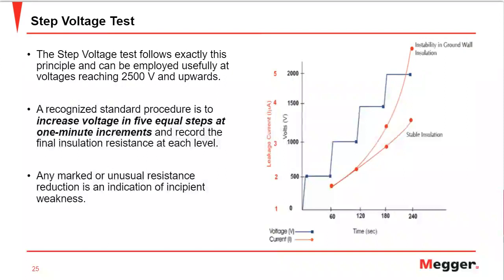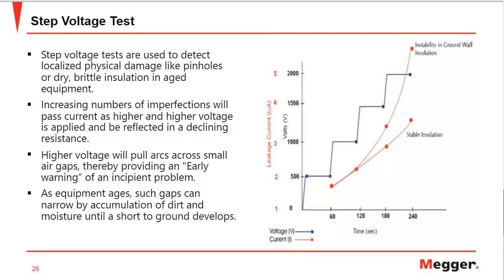Also, as we discussed previously, it increments in 5 equal steps, stays there for a minute on each step, and then calculates the total leakage current. Step voltage tests are used to detect physical damage like pinholes and brittle insulation in aged equipment as well, because we increase the voltage more than the rated voltage. If the insulation is really bad, it could instigate an arc. But also if the insulation has a little wear and tear, we would see that on the graph.